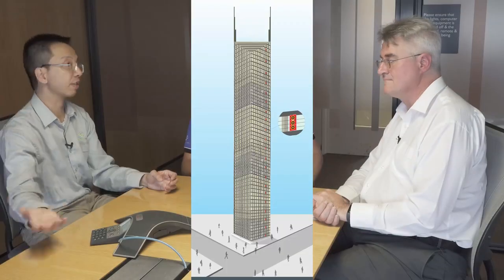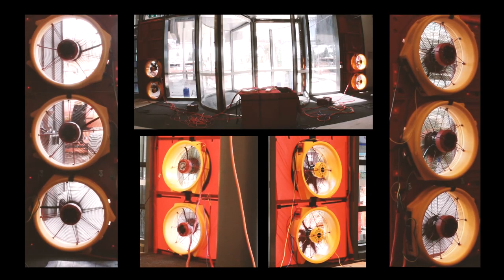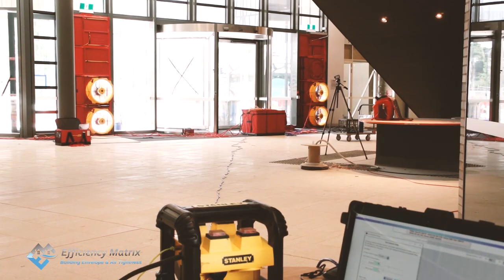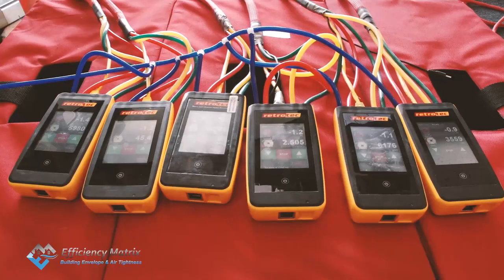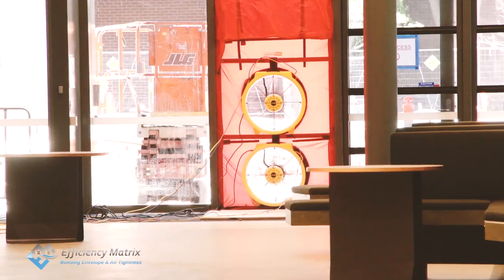For example, like a 35-story commercial building, we would set up fans on the roof level to pump into the stairwell. And in any intermediate plant room level, to also suck air in from the ambient, and then the ground, and potentially in the basement level if there is an openly ventilated car park. So we can get air from different points and even it distributes to reduce the pathway of air needs to go through. That's the best way to test because it won't have any internal leakage through areas that are not supposed to be airtight to start with.